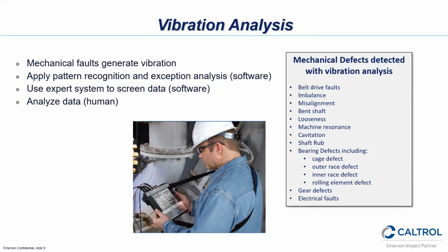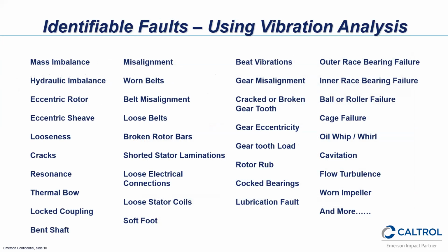But for the most part, we collect the data. The 2140 collects the data so fast now that the older analyzers used to pop up the spectrums on the screen, and you could see them displayed for a second before it would move on to the next point. But the technology has gotten so advanced that it collects the data so fast that you'll get a high alert alarm, but the view of the spectrum flashes by really fast. So most of the analysis is done back at the office after the data has been downloaded. Here are some more faults that are all identified by using vibration analysis.